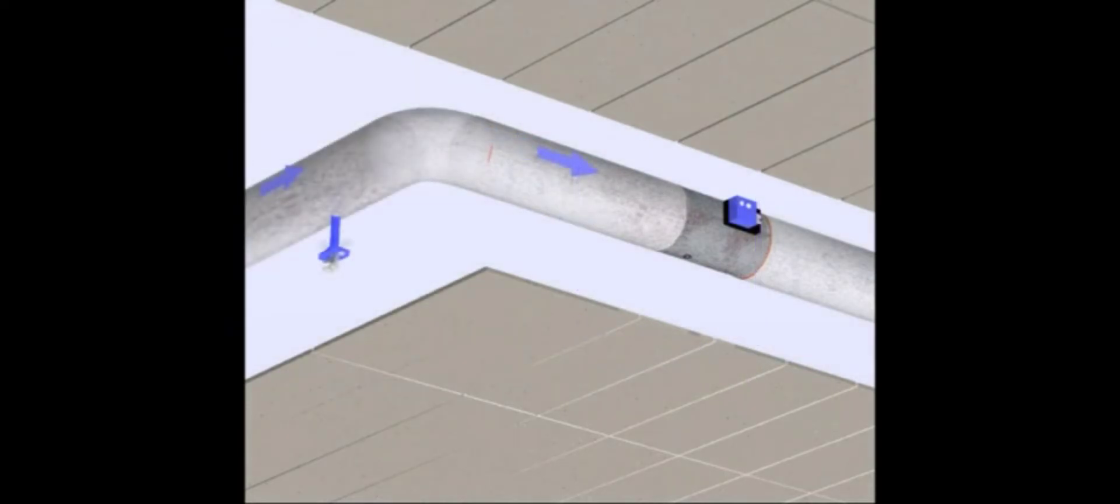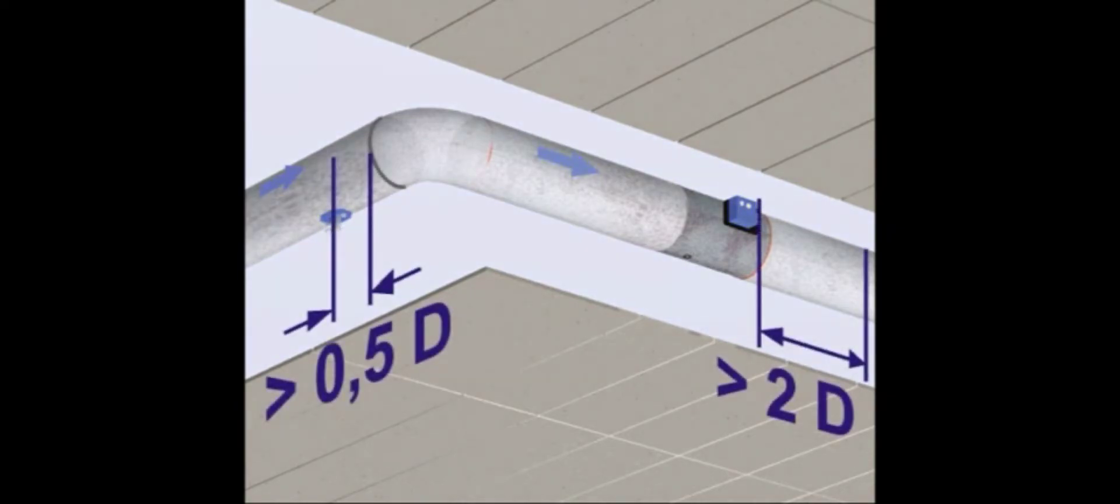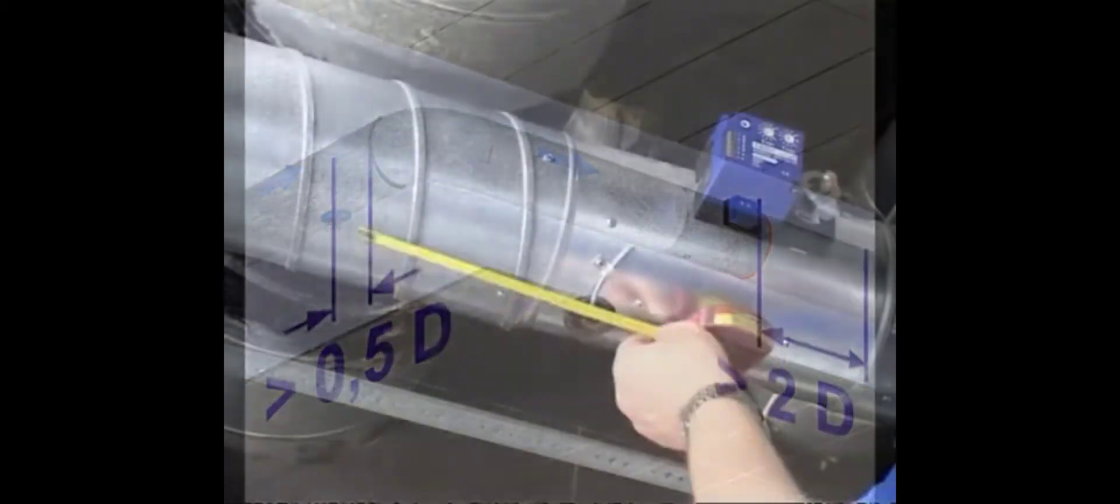Should the sensor, because of too little space, be placed for example in front of an elbow, keep a minimum distance of 0.5D from the elbow and a downstream of at least 2D behind the controller.